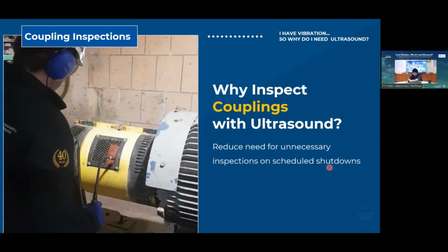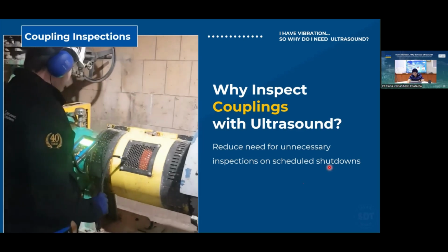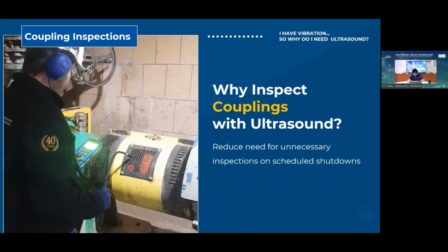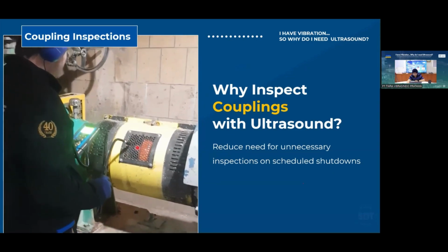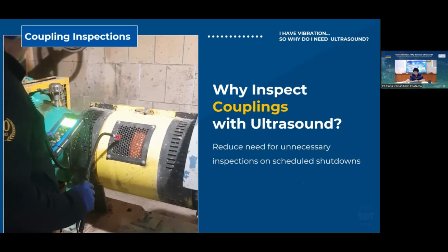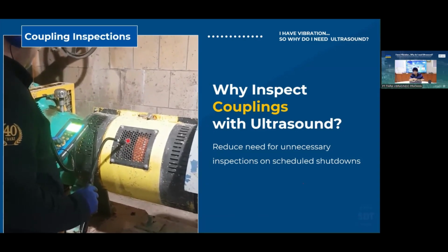In this video, you see this technician inspecting the coupling using the airborne sensor. He doesn't touch anything, but the sensor will detect the sound generated from the coupling.